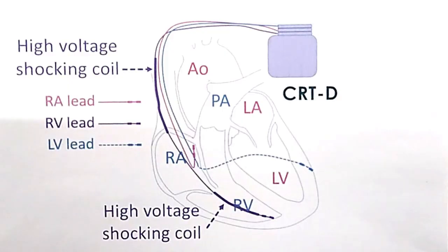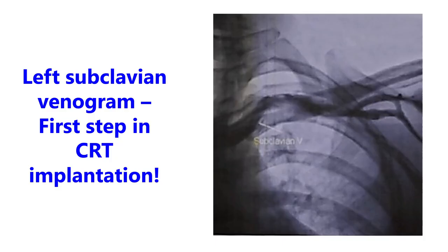So this is a combo device combining defibrillator, implantable cardioverter defibrillator, and cardiac resynchronization therapy. Obviously, it will be costlier and the battery capacity needs to be higher, and battery life will be lower if defibrillator shocks are being given in between.